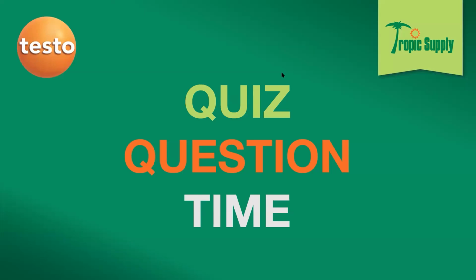Got a couple questions on the new refrigerant. I'll touch on that a little bit, but that's really a whole different topic of conversation. Basically, for those of you that are not aware, and hopefully you are by now, there's an expected refrigerant change coming January 1st of 2025. Most of your residential equipment manufacturers, your conventional equipment manufacturers, are going to be switching to either R454B or R32. Typically, we're looking at R454B in most conventional style equipment and R32 in mini split style equipment.